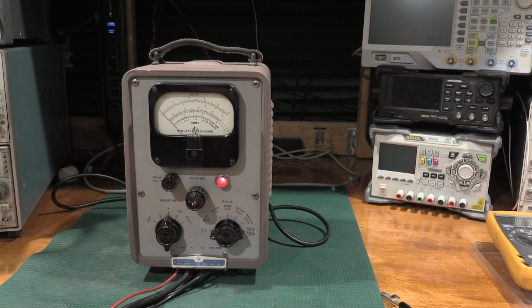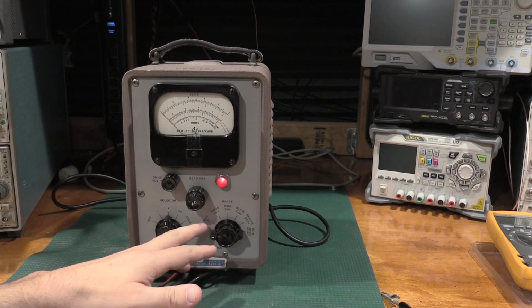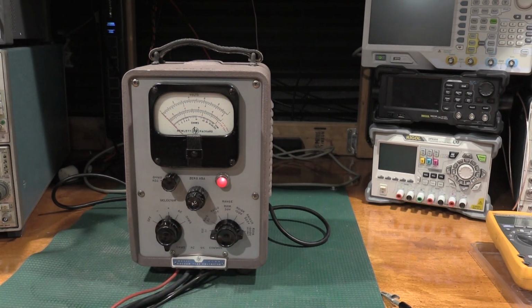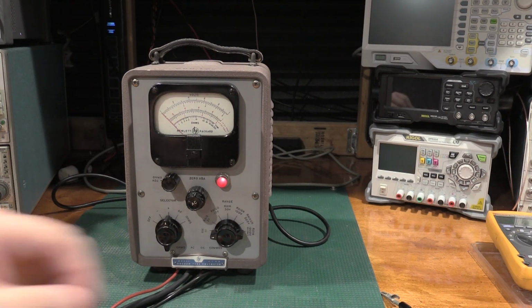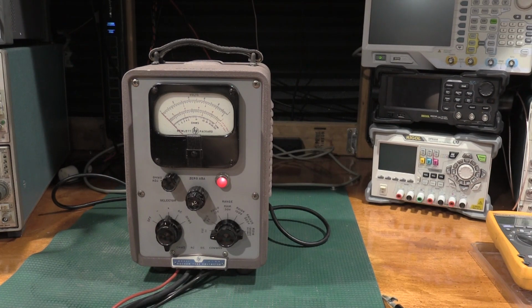For DC, I believe you calibrate the 1 volt range, and then everything else is calibrated against the 1 volt range. And in AC, you have calibration points for 1 volt, 3 volt, 10 volt, 30, 100, and 300. So you actually calibrate it on every range. And then we'll also touch up the ohms range as well, because this is an incredibly sensitive ohms meter.